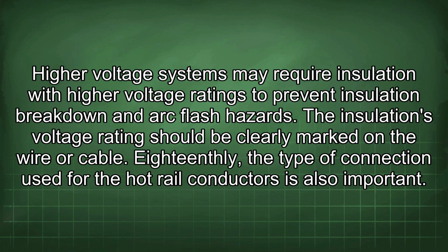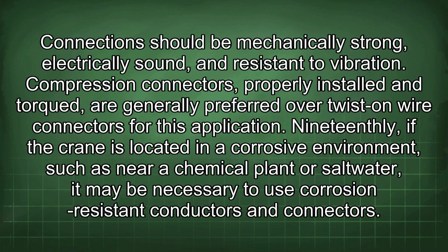18thly, the type of connection used for the hot rail conductors is also important. Connections should be mechanically strong, electrically sound, and resistant to vibration. Compression connectors, properly installed and torqued, are generally preferred over twist-on wire connectors for this application.